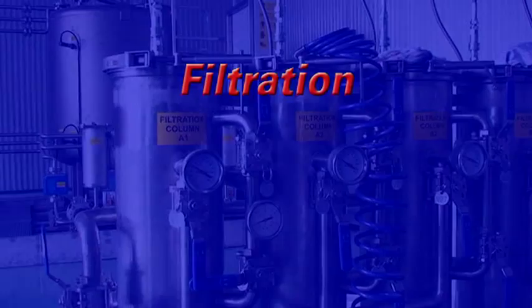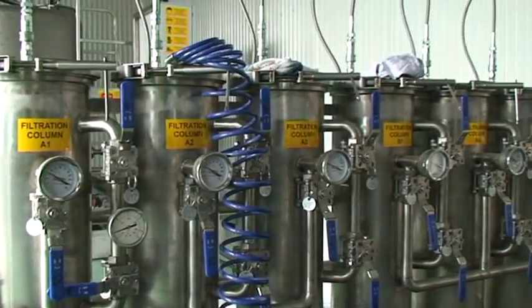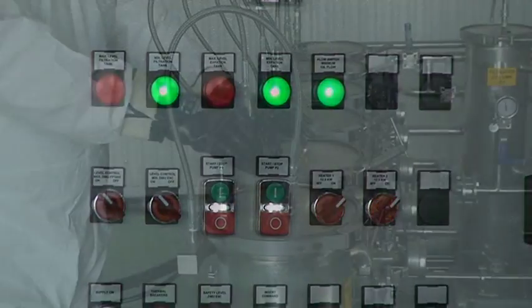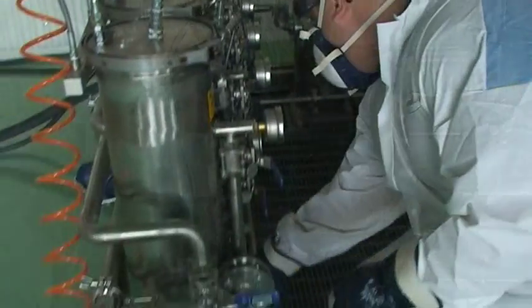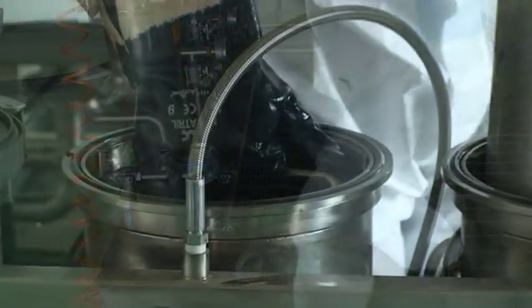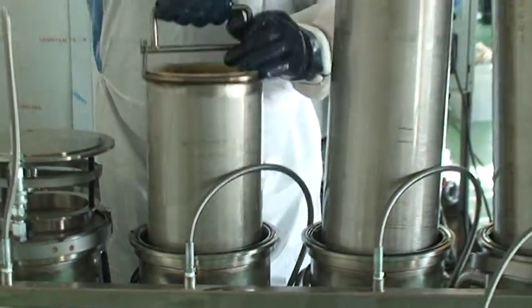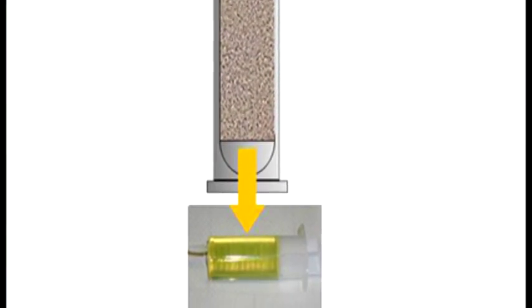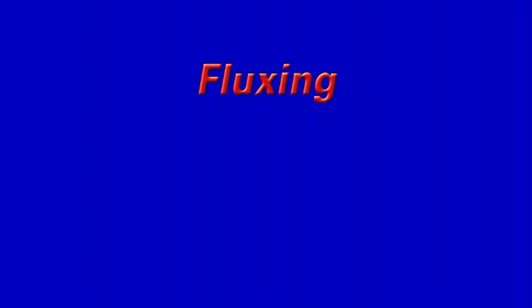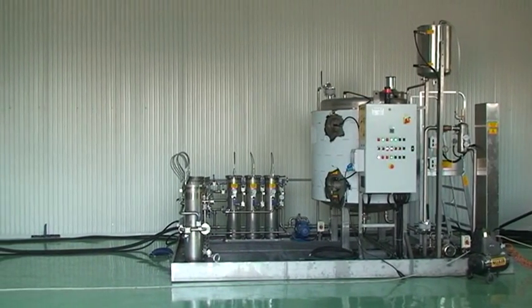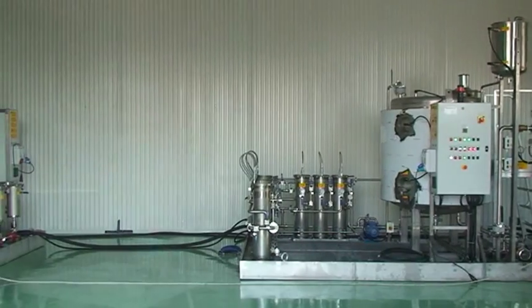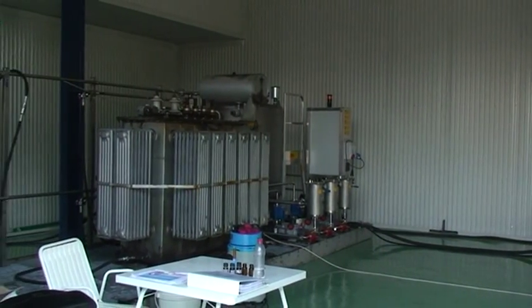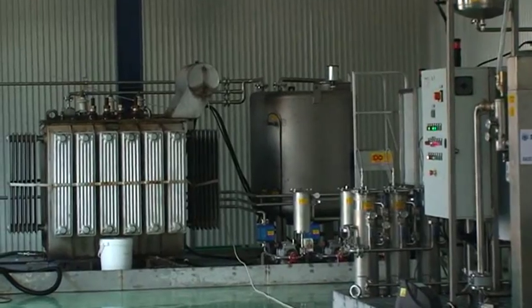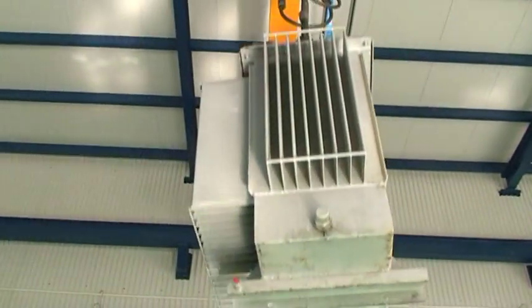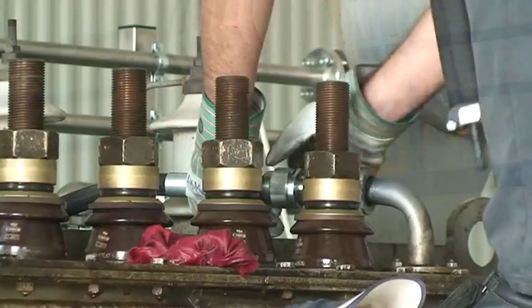Filtration. Filtration of suspended and polar compounds from the oil takes place in the filtering unit through continuous circulation and percolation under pressure in columns filled with active clays. Fluxing. The cleaned oil is transferred to the fluxing platform, where the transformer's carcasses are flushed through continuous circulation and fluxing with hot mineral oil, which enables maximum extraction of the PCB residues from the porous parts.